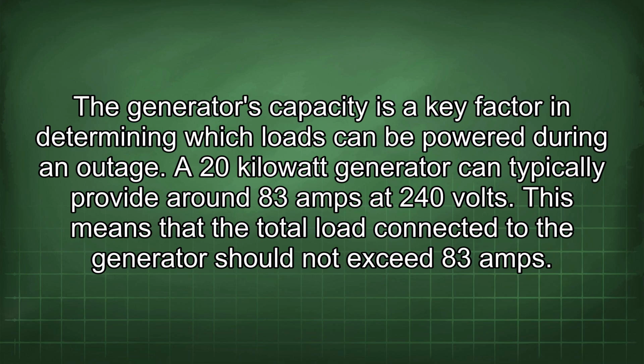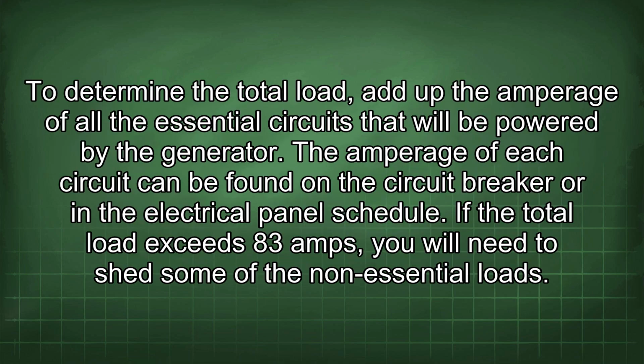A 20 kilowatt generator can typically provide around 83 amps at 240 volts. This means that the total load connected to the generator should not exceed 83 amps. To determine the total load, add up the amperage of all the essential circuits that will be powered by the generator. The amperage of each circuit can be found in the circuit breaker or in the electrical panel schedule. If the total load exceeds 83 amps, you will need to shed some of the non-essential loads.